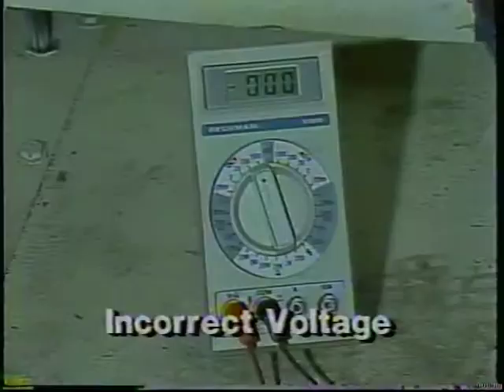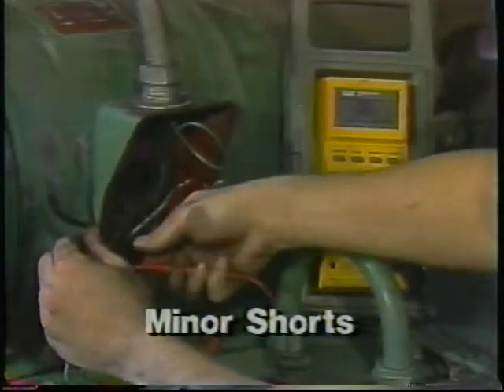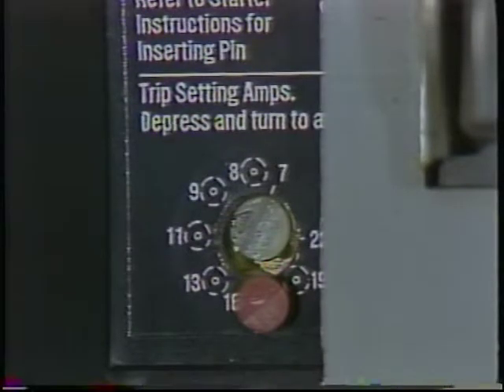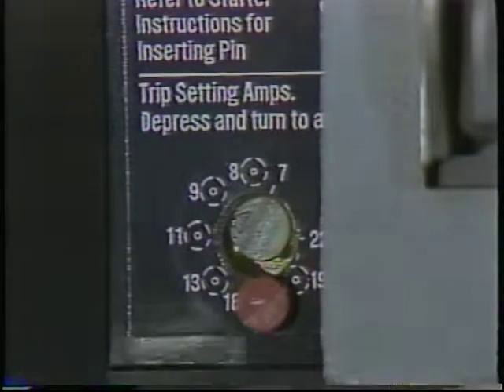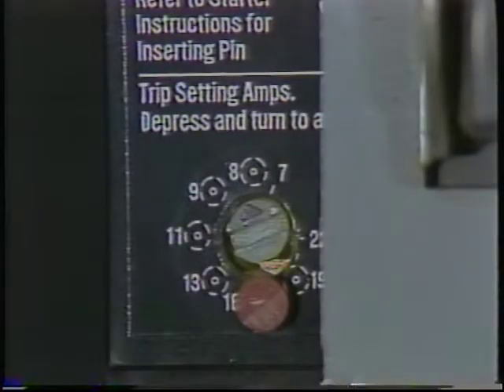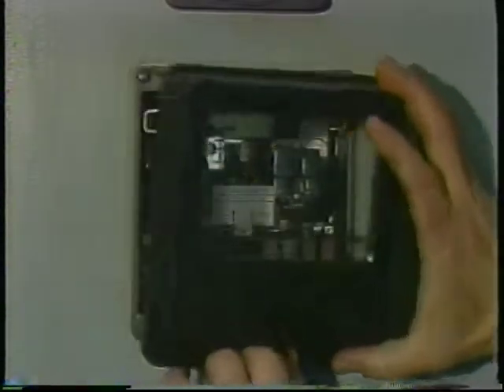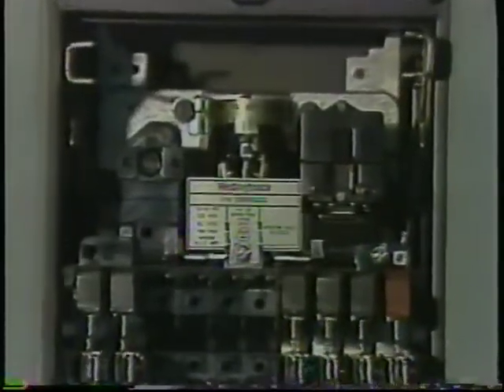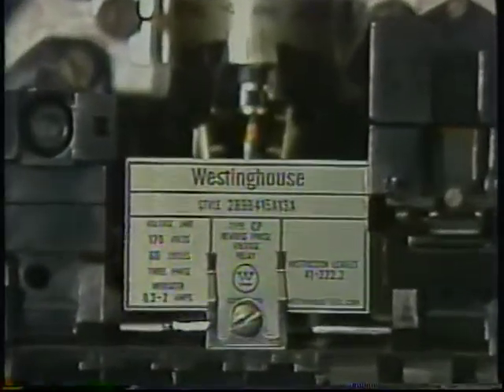In most cases, high temperature in a motor is a result of high current, and as we have seen, high current to a motor can be caused by many things. Mechanical problems in the motor or load which require it to produce too much torque, low or high supply voltage, zero phase voltage, and current leakage through minor shorts. The overload breakers are supposed to protect the motor from overheating caused by high current, but sometimes they do not respond quickly enough. On some equipment, low voltage and phase loss relays also work to protect the motor from damage. But no kind of protective equipment can prevent motor damage in all situations. If dirt prevents heat loss, for example, a motor may overheat without tripping its overload breaker.